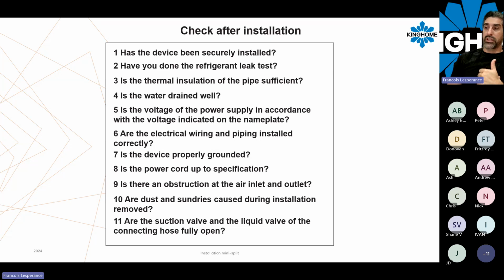Making sure also you don't have any obstruction in the air inlet or air outlet, and don't have an excess of dust somewhere. If a coil is very dirty, you have cleaned it up with water, and that's good enough. And also make sure your suction valve and liquid valve are fully open.